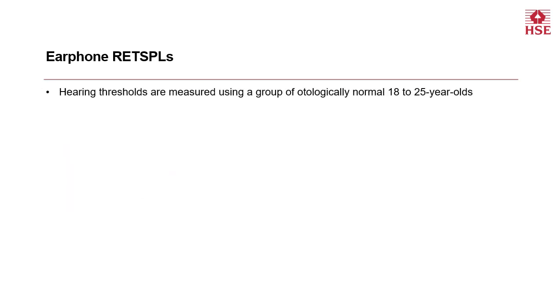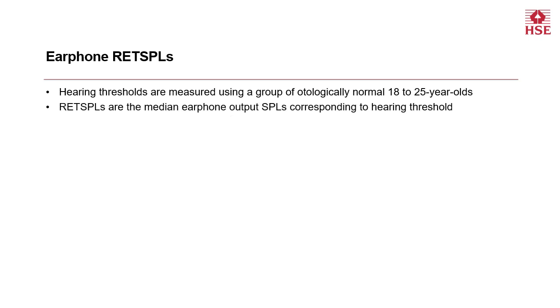To obtain the reference equivalent threshold sound pressure levels for an earphone, the hearing thresholds are measured using a group of otologically normal 18 to 25-year-olds. The RETSPLs are the median earphone output sound pressure levels corresponding to hearing threshold. They define 0 dB hearing level for a particular earphone model.